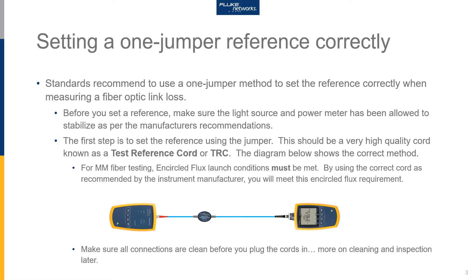The next step in the reference process is to use the jumper cord to set the reference. The cord needs to be a test reference cord — we sometimes refer to these as TRCs — not a patch cord. You can't use patch cords for making good loss measurements because they contribute too much loss. Test reference cords contribute very little loss: less than 0.1 dB for multimode cords and 0.2 dB for single mode cords.